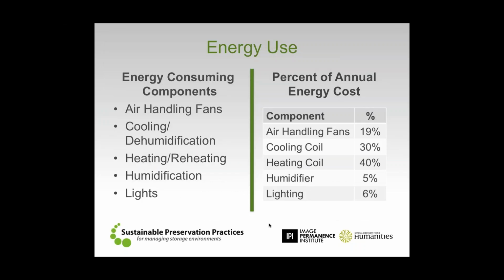These numbers actually come from Peter Herzog, a partner of ours that we've worked with for a number of years here at IPI. Over the course of his 30 or 40 years of looking at mechanical systems, buildings and energy usage, he started pulling together numbers to figure out just how much energy each of these typical components tends to use, because we have our expectations and, shall we say, assumptions as we move into this. What Peter found over time is that, looking at the individual components, roughly 20% of our annual energy cost for the mechanical system is used at the air handling fan, whether it's a supply fan or a return fan. Another 30% of that annual cost is used by the cooling coil, with 40% over the course of a year used at a heating coil.